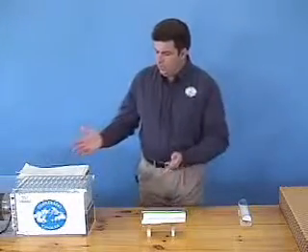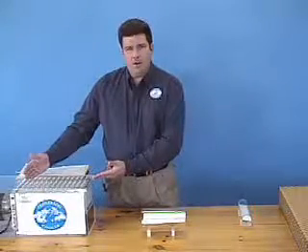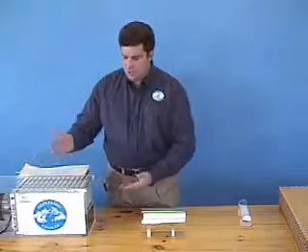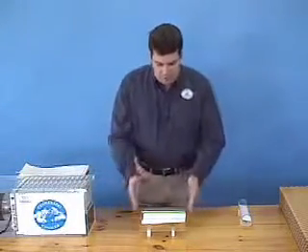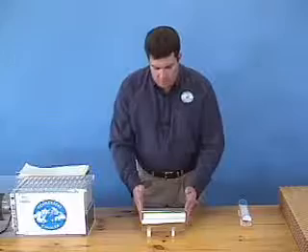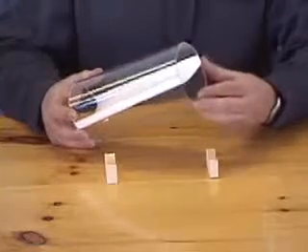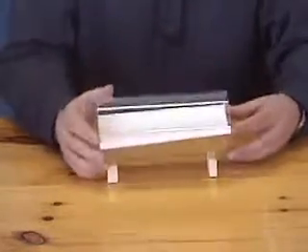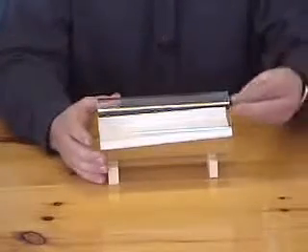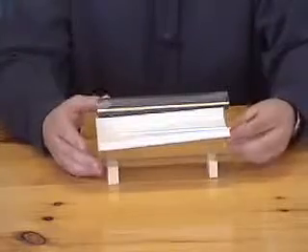But we know that Coolerado coolers can cool below the wet bulb temperature, and our theoretical limitation is cooling towards the dew point temperature of air. Let's go back to your theoretical long tube heat and mass exchanger. When the air comes out of the dry side of the pipe, it will be cooler, and its wet bulb temperature will have been lowered. You'll throw away the humid air from the wet side to the atmosphere.